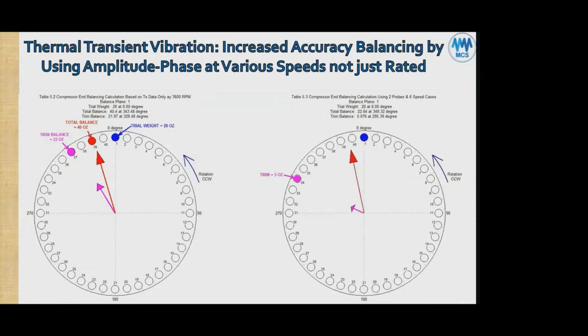If you solved external problems, going back to our initial discussion, the third slide, is first solve other issues, nonlinearities in the machine, bearings and others. But coming back to that, say you have solved them, then the author here says, okay, use various balancing speeds to get a better, more accurate idea of the phase angle of the unbalance here. So don't only use the 3,600 RPM.